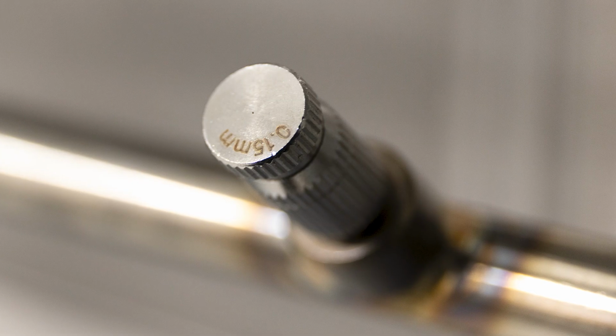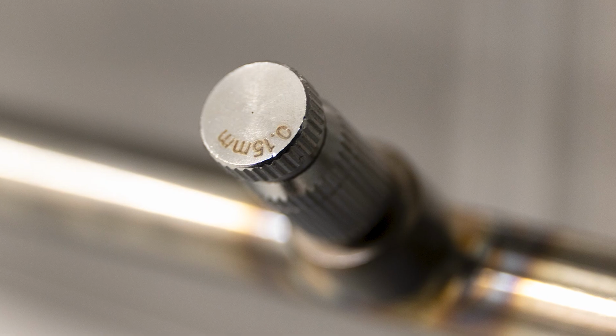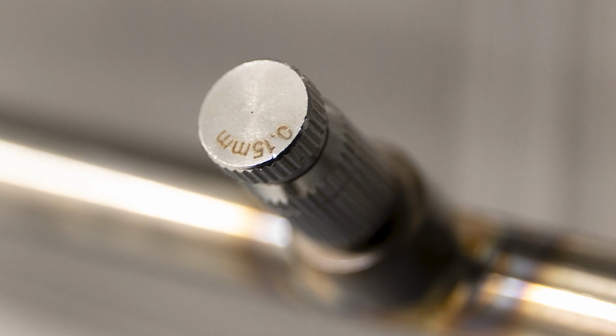The other thing is, if you're spraying water, you need clean water. You need reverse osmosis or DI water typically, because if you're shattering it through a small little nozzle, you don't want to cause mineral deposits to stay behind and cause it to clog up and not work. It's going to drive the pressure up. It's not going to spray mineral deposits around, so you need to remove the mineral deposits ahead of time.